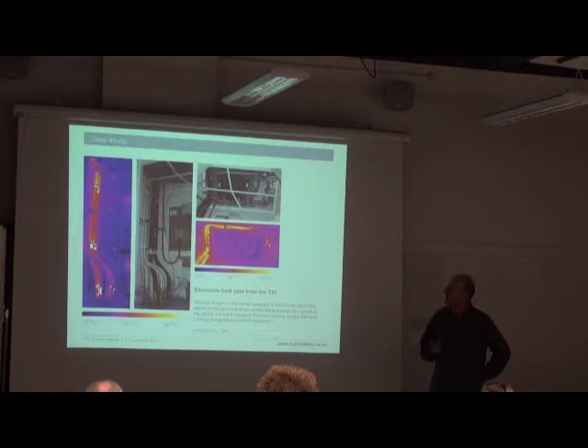And then this is the pipework distributing the hot water and the domestic heating system. And the only reason for overheating in this dwelling was a combination of this heat source in the cupboard with the HIU and the fact that it had a very poor ventilation strategy.